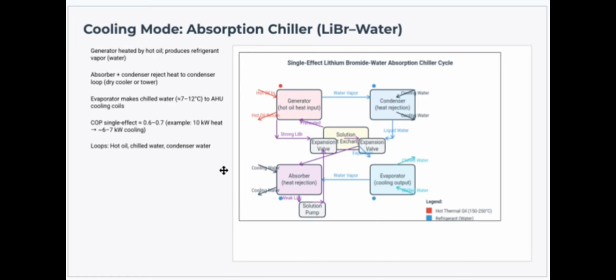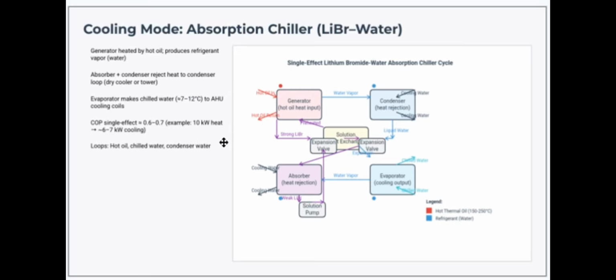The cooling mode, absorption chiller: generator heated by hot oil produces refrigerant vapor, absorber plus condenser reject heat to the condenser loop, dry cooler or tower. Evaporator makes chilled water to AHU cooling coils. COP single effect is around 0.6 to 0.7. The loops are hot oil, chilled water, and condenser water.